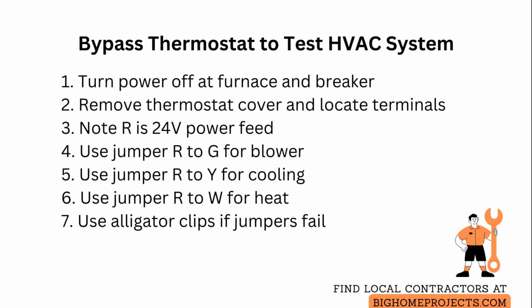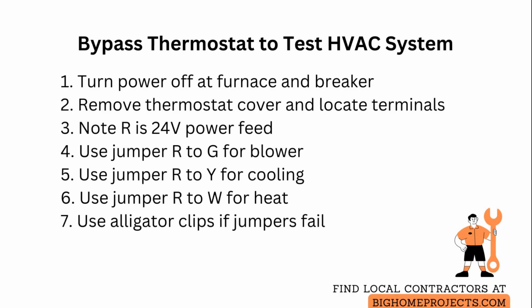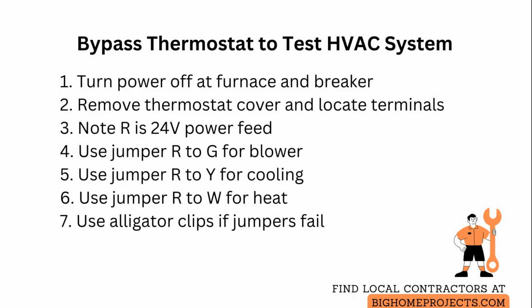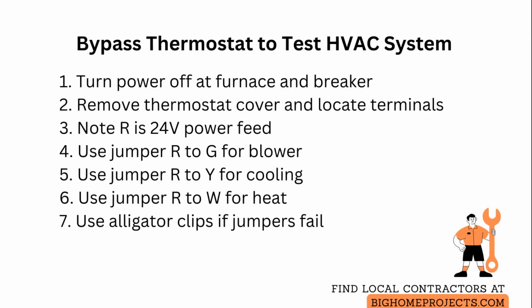Use a small screwdriver or a purpose-made jumper, such as a magnet jumper, to briefly connect R to G to force the blower on, R to Y to call for cooling, or R to W to call for heat. Hold each jumper only long enough to confirm operation and then remove it.